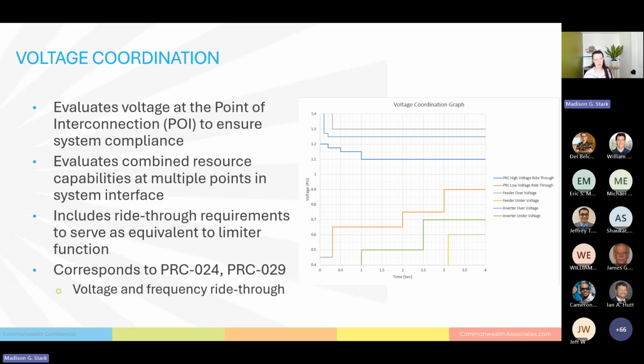An interesting note: because of the way PRC 19 is written right now, the voltage requirements correspond very closely, if not identically, to the ride-through requirements in PRC 24 and PRC 29. PRC 24 and 29 do not take the place of PRC 19. These are still separate requirements, but there is a lot of overlap in what those requirements look like right now. So it's just an interesting thing. PRC 24 and 29 are in relation to the voltage and frequency ride-through requirements for generating systems.